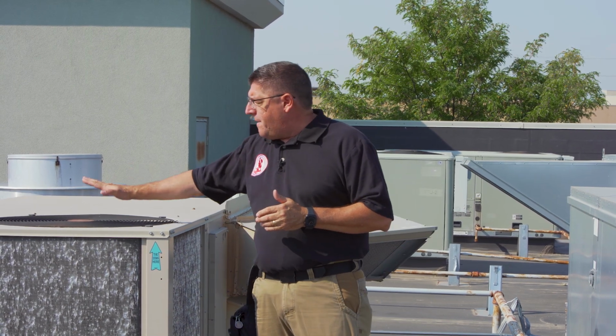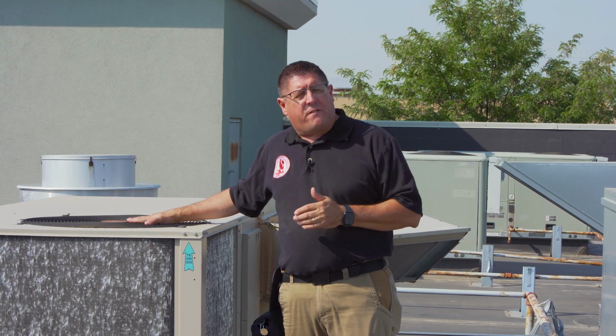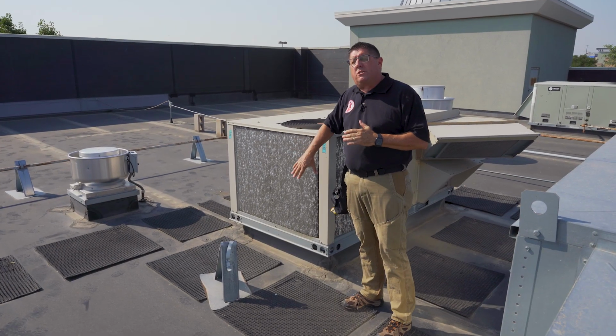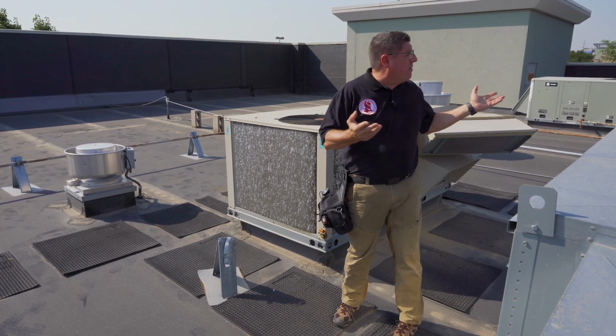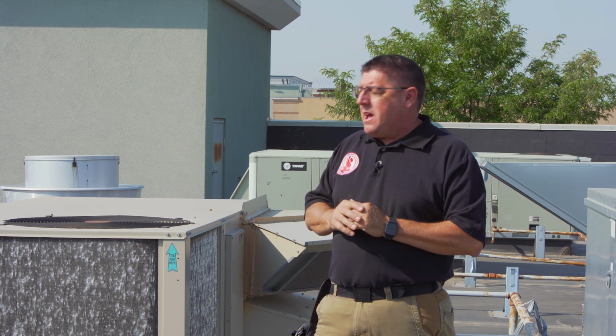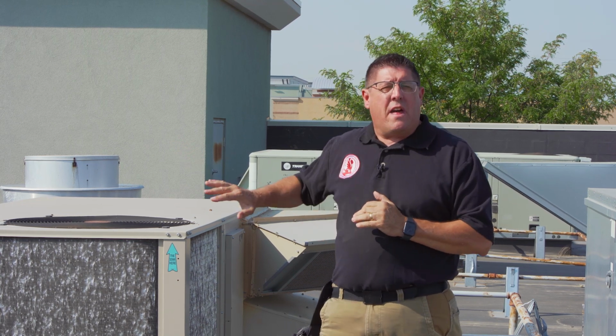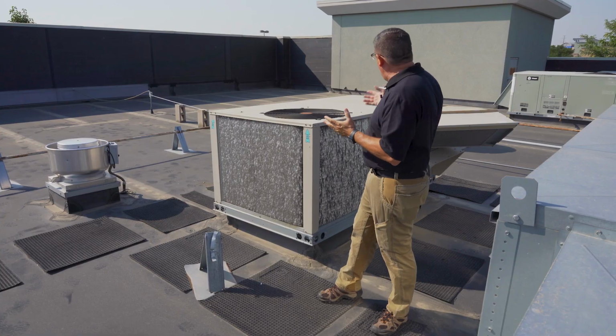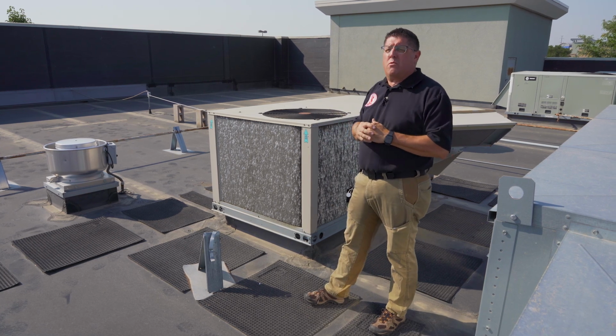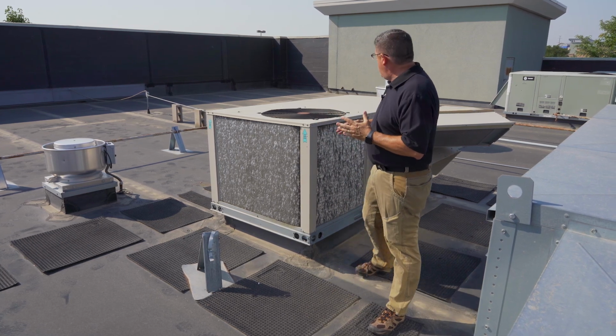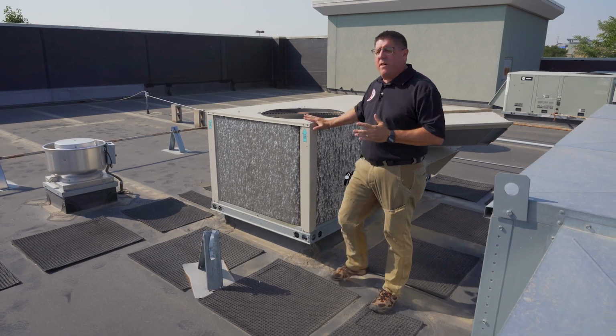And then on top of it, we have the fan, as well as the fan guard. They do make fin guards to protect it from hail. I mean, we are out in the absolute outdoors, and so there's no protection on this appliance. Then lastly, we want to look at the overall condition, make sure it's not rusted, make sure it's not damaged, make sure there's no water ponding on the top of it, and then after that, it's all set for just turning it on and operating it. We'll do that from the inside.